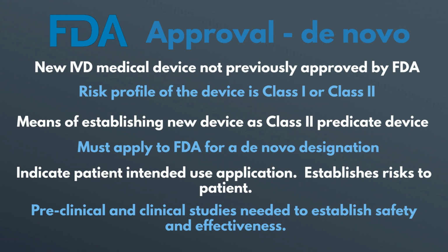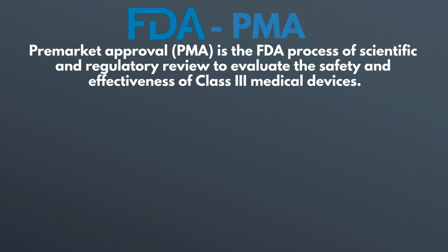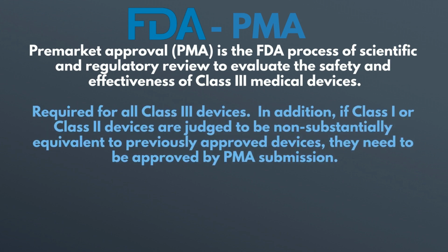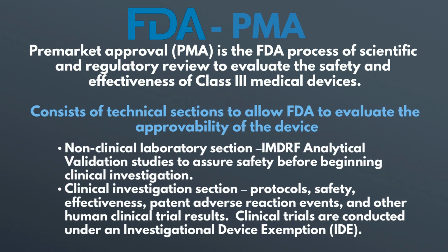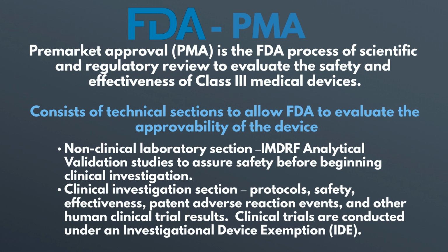in order to get a de novo application for a product. Class 3 devices are the riskiest of devices. SaMD devices that are being developed as Class 3 require a PMA approval. And that means that you have to evaluate the safety and the efficacy of these Class 3 medical devices with more extensive studies in order to demonstrate this.